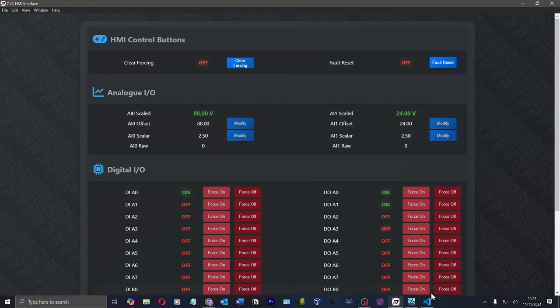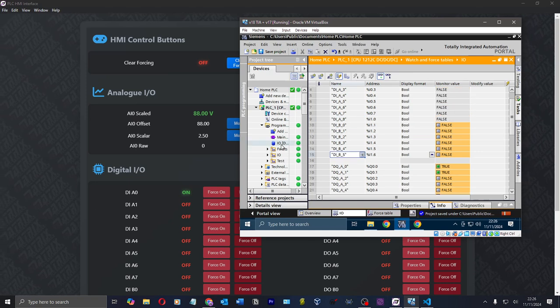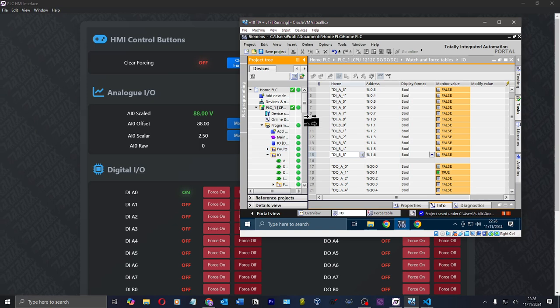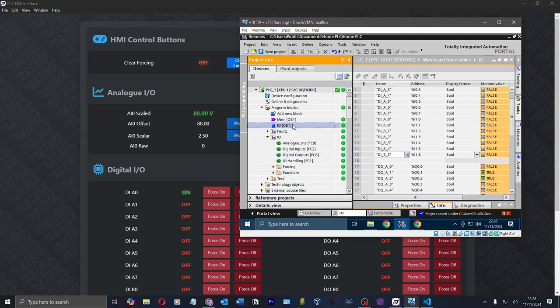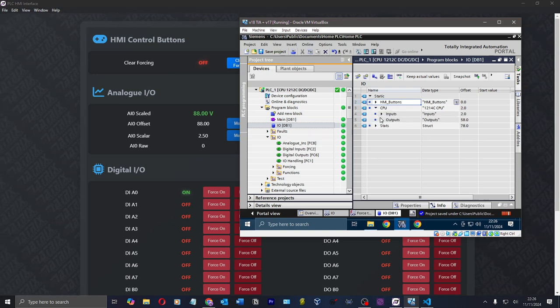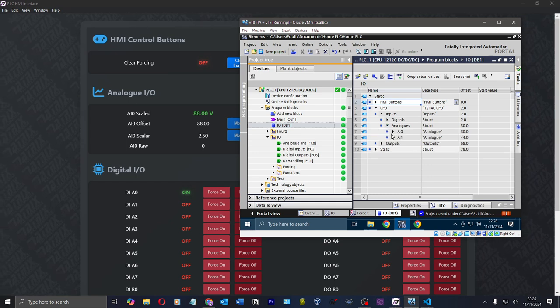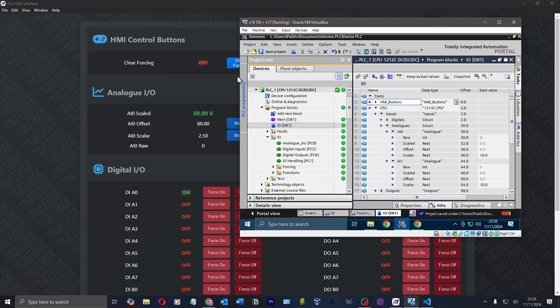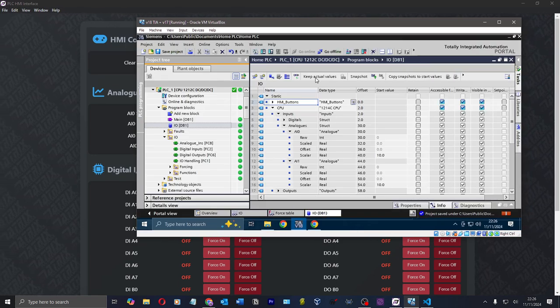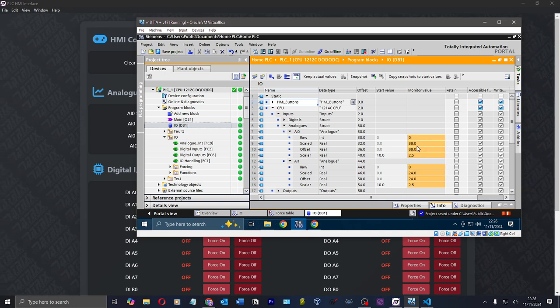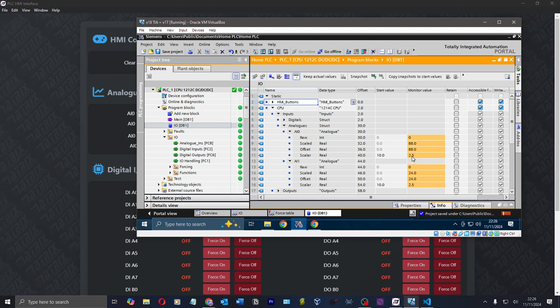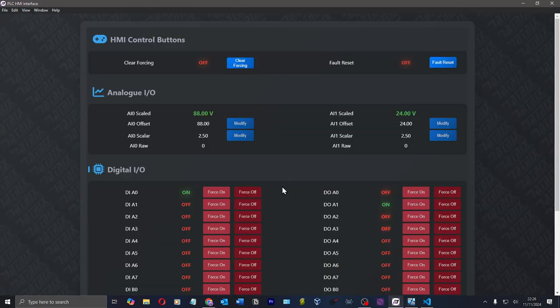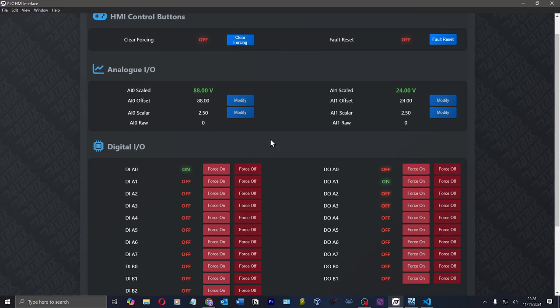These values are written to the PLC. So if I go to the PLC and I go to CPU, inputs, analogs, and I monitor that. You can see I've got 88 scaled, 88 offset, scale of 2.5, 24, 2.5. All of that works in absolute beauty.